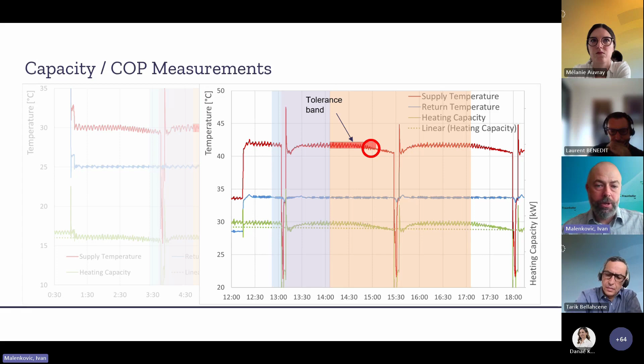This here is a diagram which shows a transient measurement, which means that it also includes defrost cycles. Again, these defrost cycles can happen in different phases of the measurement. It can also happen that your evaporator has not been completely defrosted before. So in one measurement, you will get one efficiency of the heat pump, and the next measurement might deliver another efficiency. So it means that you really have to put in a lot of effort and a lot of knowledge to know how a heat pump reacts and what to do exactly to have a completely valid result as prescribed by the standard.